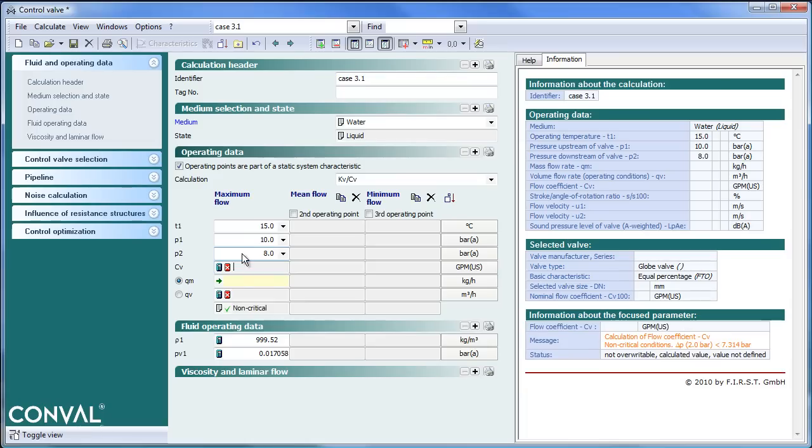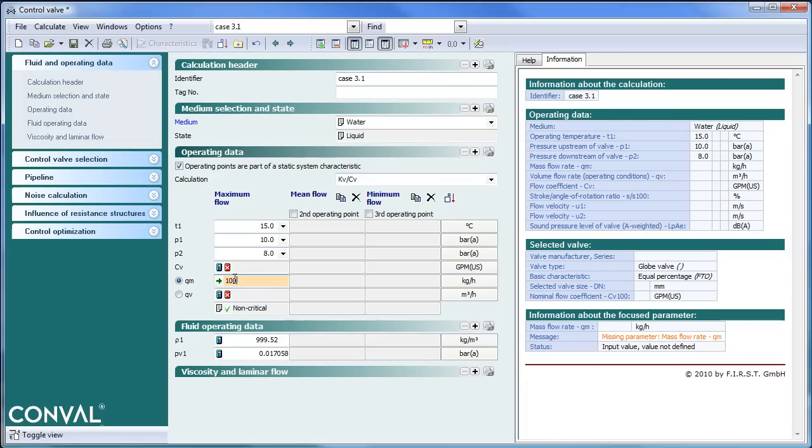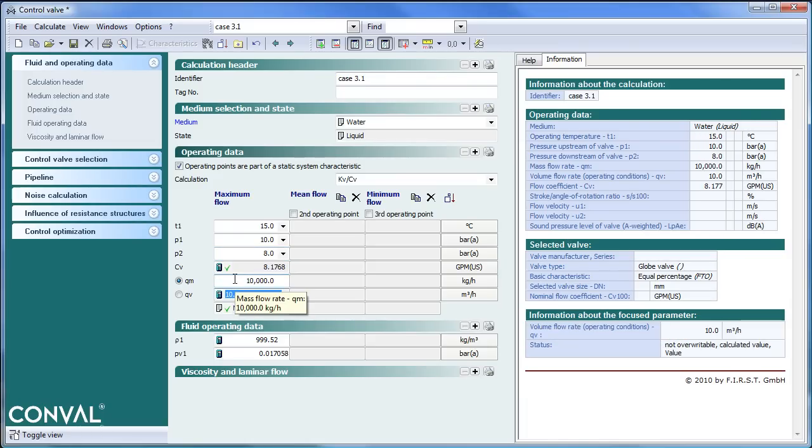Eight downstream. Mass flow ten thousand kilograms per hour. Gives us a CV of 8.2.